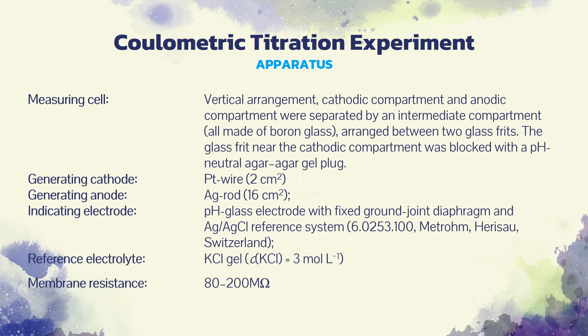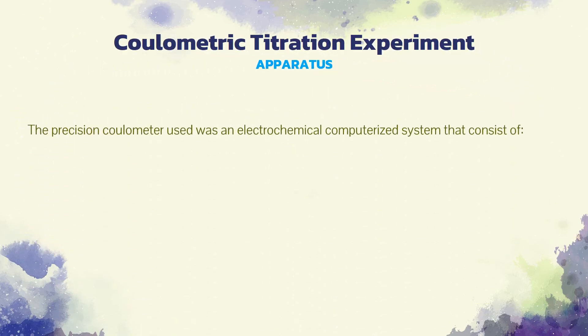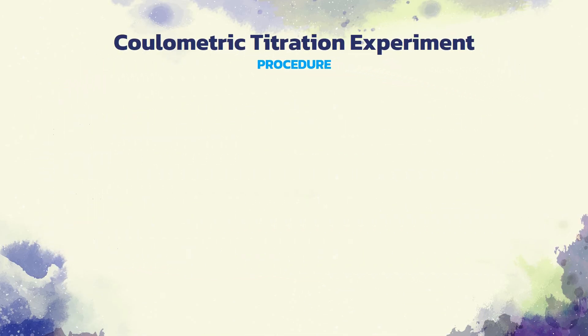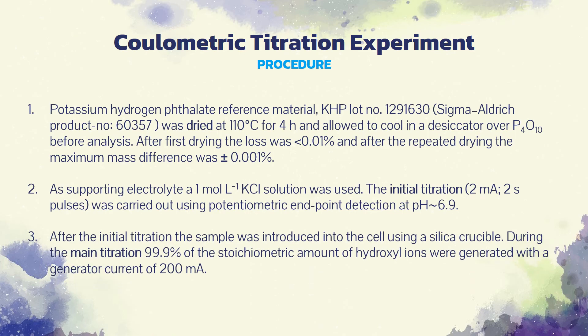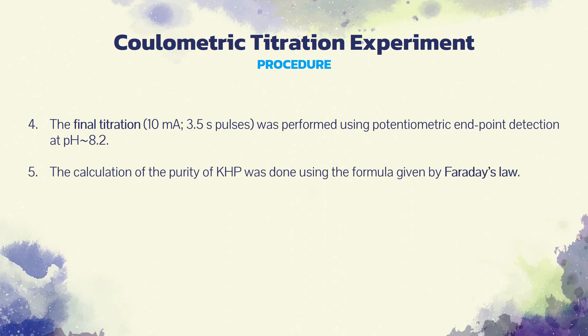The precision coulometry used was an electrochemical computerized system that consists of a constant current source, an indication unit, a valve unit, and a piston burette. For the measurements, four calibrated devices were used: an analytical micro balance, a timer, a multimeter, and a resistor. The experimental procedure involves drying of the sample, performing the initial, main, and final titrations, and calculation of purity and measurement uncertainty.